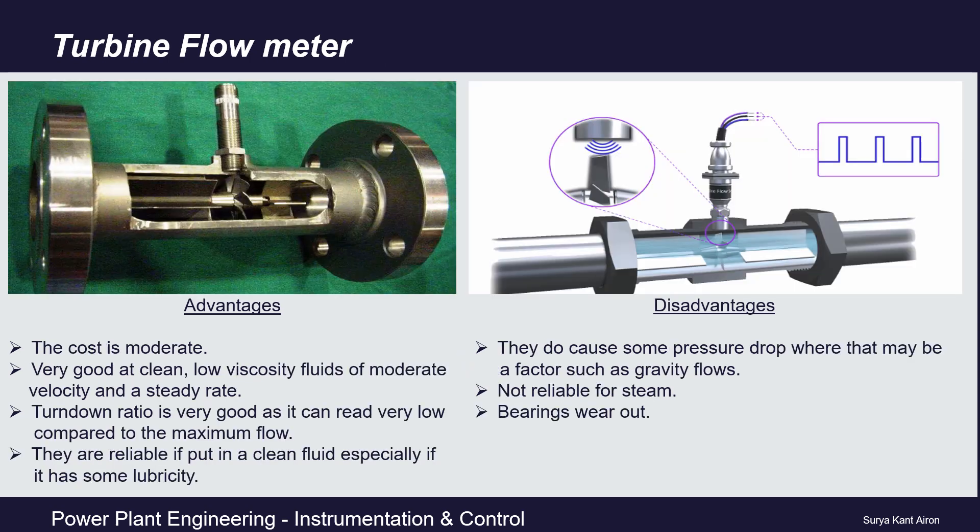Turbine flow meters use the mechanical energy of the liquid to rotate a rotor placed in the center of the meter. The fluid flowing through the turbine flow meter exerts pressure on this rotor, causing it to rotate. The rotational speed is directly proportional to the velocity of the fluid traveling through the meter. This rotation per minute is measured using a non-contact proximity sensor, which gives an indication of fluid velocity, further calibrated to provide flow rate.